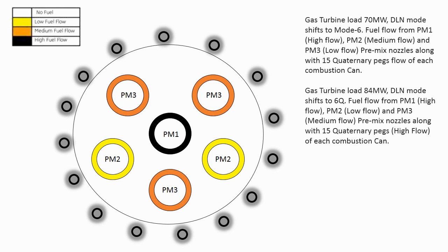When 7FA gas turbine load reaches 70 megawatt, DLN mode shifts from mode 3E to mode 6. Fuel flows from PM1, PM2, and PM3 of each combustion can along with 15 quaternary pegs. Note that fuel flow is high from PM1, low from PM2, while from PM3 fuel flow is medium.